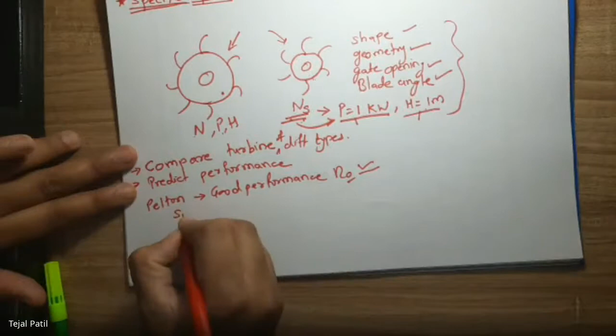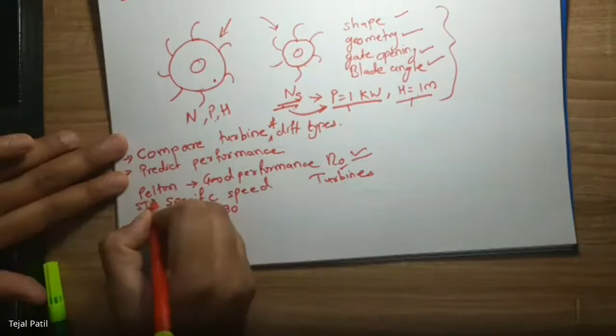Specific speed, and based on it, the turbines. Okay, let's say your specific speed is 8.5 to 30. Okay, so this is in SI unit, of course, because if you are using another unit, like instead of kilowatt you are using some other, or instead of meter you are using centimeter or other thing, of course the value will change. So let's say your specific speed is in between 8.5 to 30. Then the turbine which you should use is a Pelton turbine, but with only one jet.